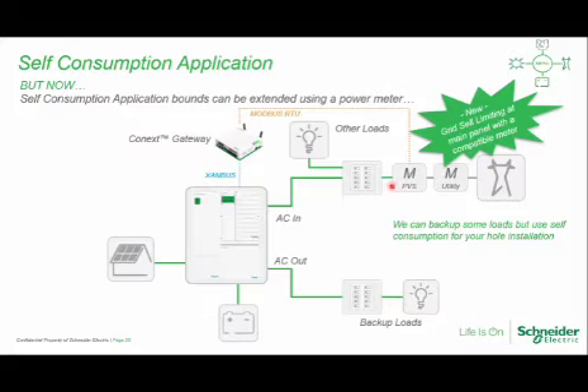Self-consumption basically means you're not selling this excess solar power back to the utility, because in some regions you're not allowed to sell excess power to the utility, so you have to limit it. With this self-consumption application on the XW Pro, you have some additional devices you connect to the system, which let you accomplish self-consumption for your full loads, both critical and non-critical, while still maintaining self-consumption rules.